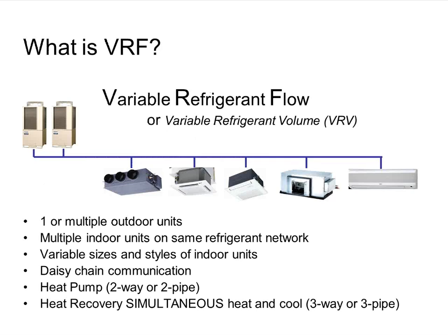So what is VRF? VRF, as most of you guys know, stands for Variable Refrigerant Flow Systems. One manufacturer also calls it VRV, and that's become kind of a Kleenex type term. But the official name is Variable Refrigerant Flow Systems. What this basically means is I have a single outdoor unit serving multiple indoor evaporator coils. Sometimes we also even have 2 or 3 outdoor units, manifolded together refrigerant-wise, serving multiple indoor units. So we run these outdoor units at different speeds, and the indoor units will use as much refrigerant as they need. And if they need less, they tell the outdoor units, hey, we need less refrigerant volume, slow it down.